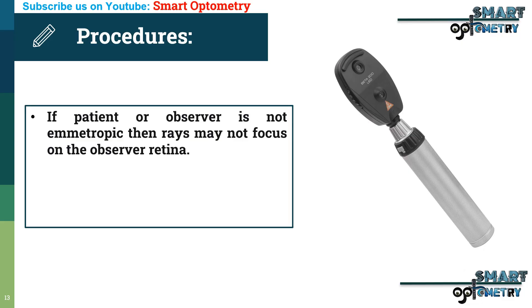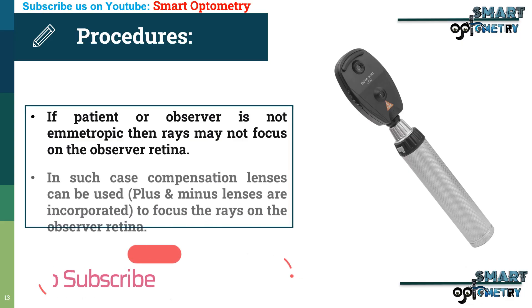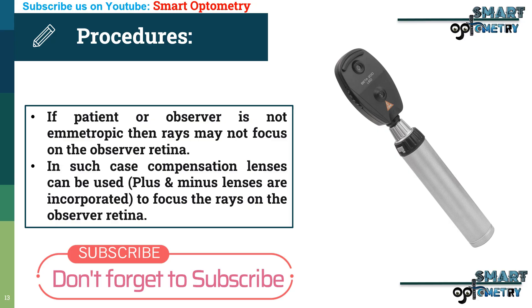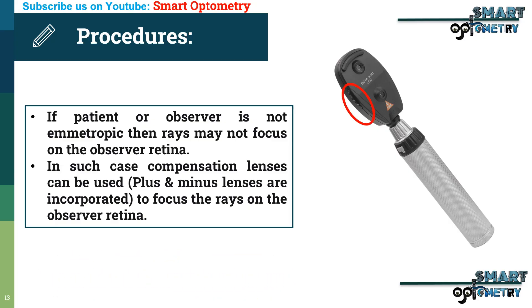If the patient and observer are not emmetropic, then rays may not focus on the observer's retina. In such a case, compensation lenses can be used to focus the rays on the observer's retina. Compensation lenses — spherical plus and minus lenses — are incorporated inside the ophthalmoscope. As only spherical plus and minus lenses are incorporated, if any patient or observer has cylinder power, we can simply use the spherical equivalent.